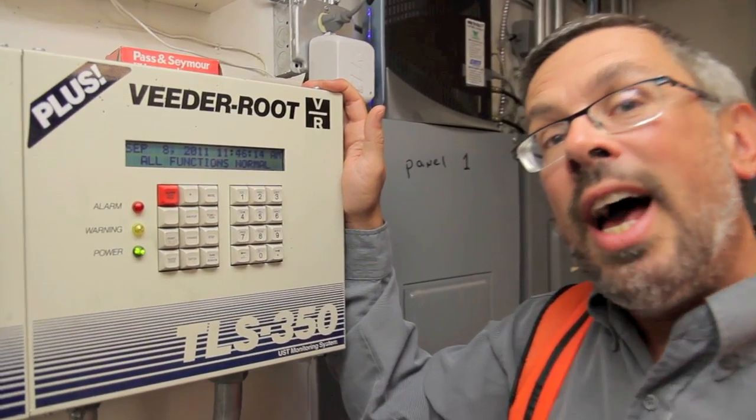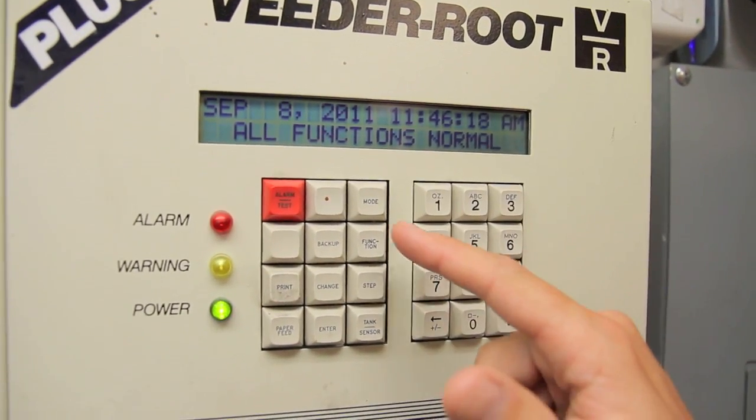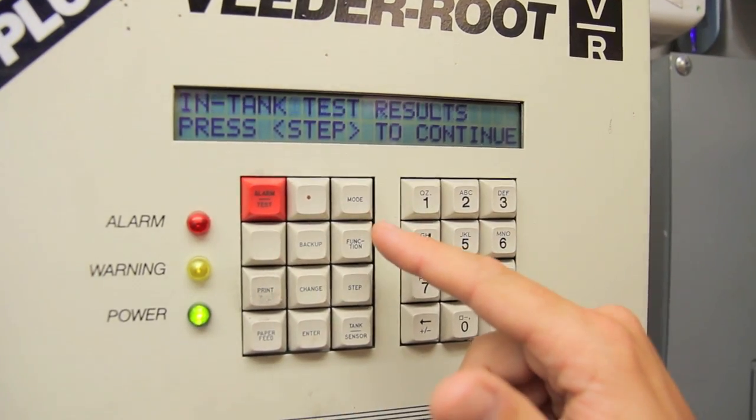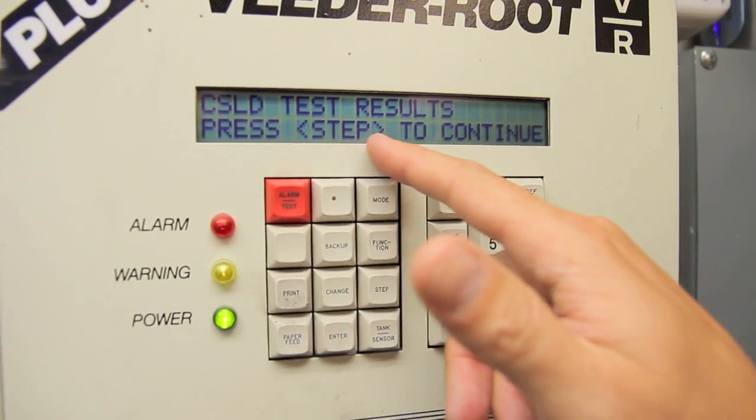It says all functions normal. How do we get the last test result? If you go to the normal operating mode and hit function a couple times, this one actually says CSLD test results. That stands for continuous statistical leak detection.